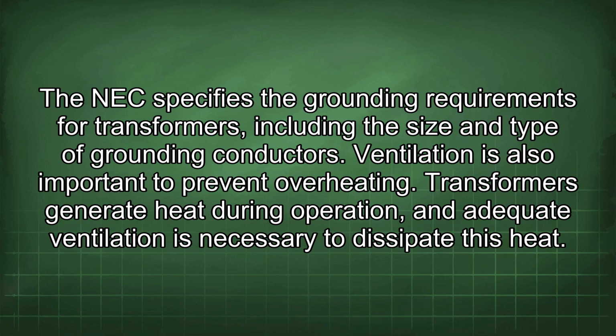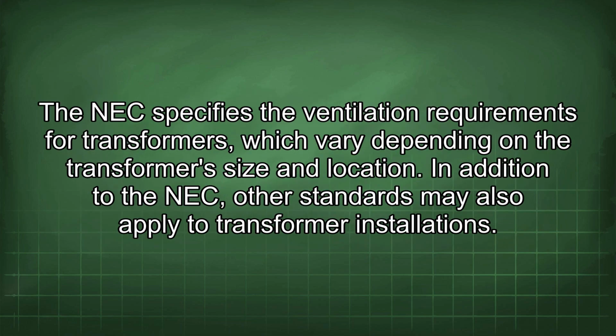Ventilation is also important to prevent overheating. Transformers generate heat during operation, and adequate ventilation is necessary to dissipate this heat. The NEC specifies the ventilation requirements for transformers, which vary depending on the transformer size and location.